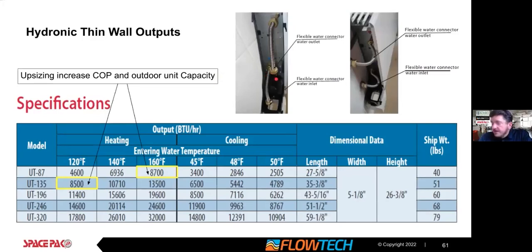I believe on that. And then, design flexibility. You're needing to satisfy an 8,000 BTU load. You can do that with 160 degree water, or you can increase your unit size slightly, physical size raises, but now you're down to 120 degree water temperature. So it's a great efficiency to look at sizing.